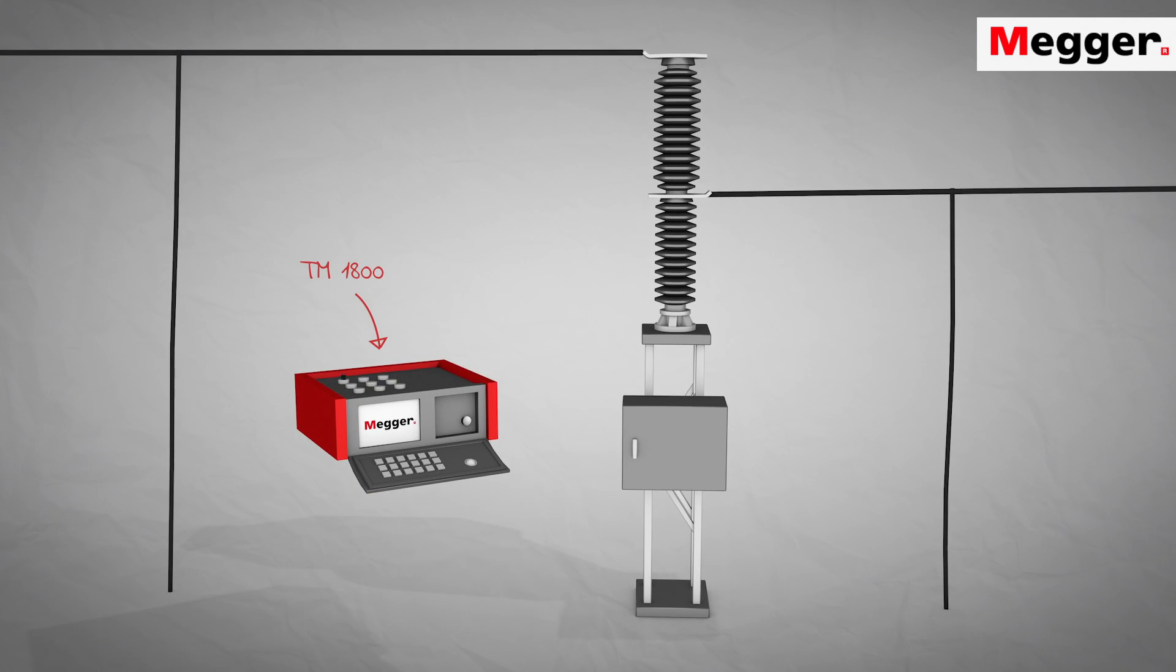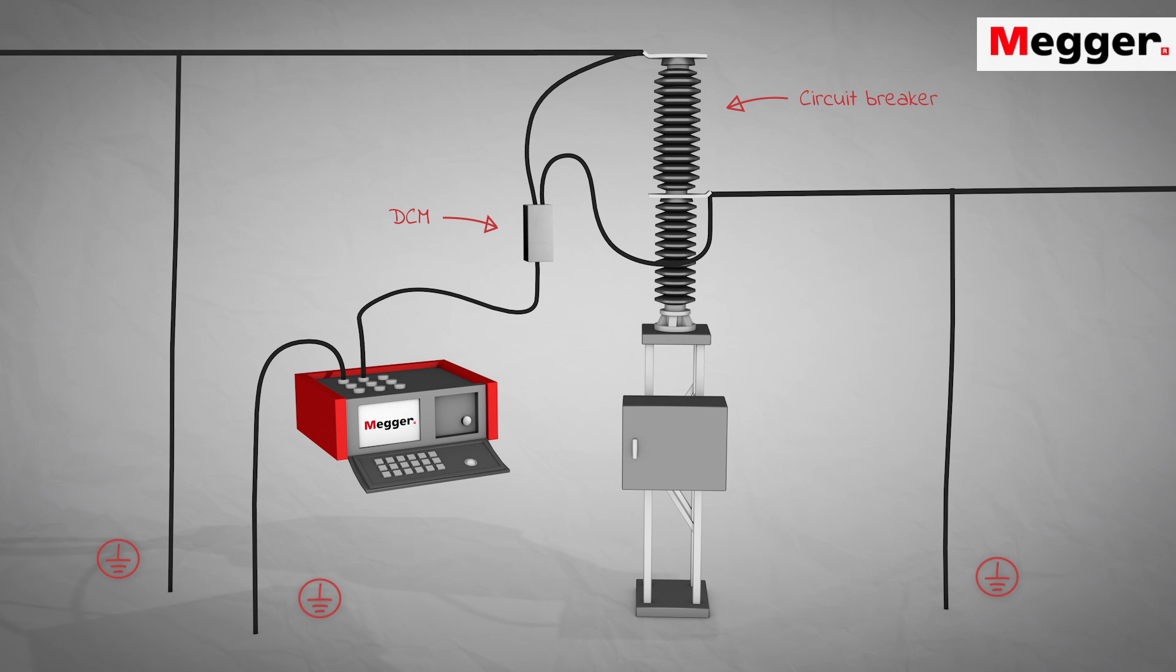Start by connecting the TM1800 to ground. Connect the DCM cables to the circuit breaker. Connect the control cables to the circuit breaker's trip and close coil circuits.